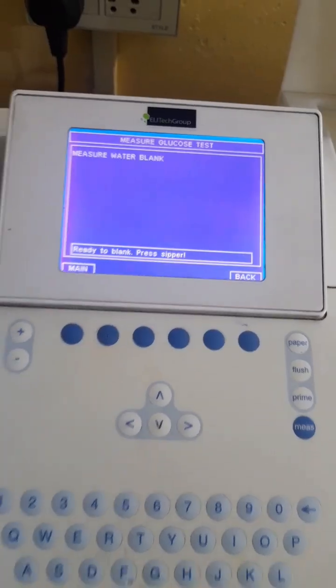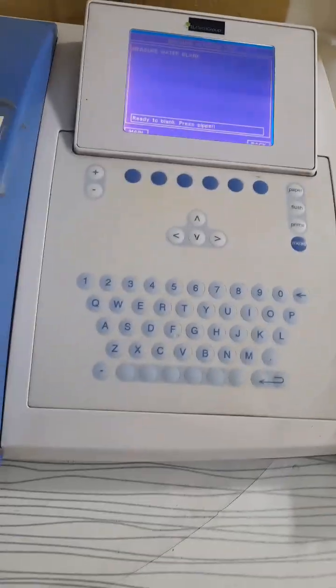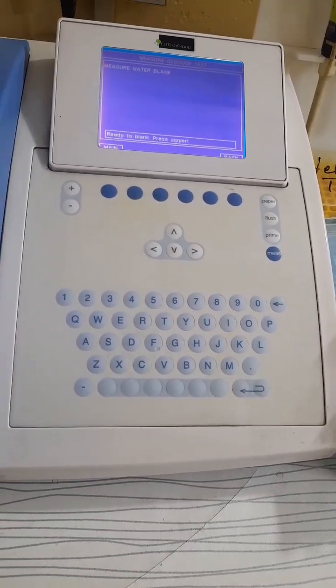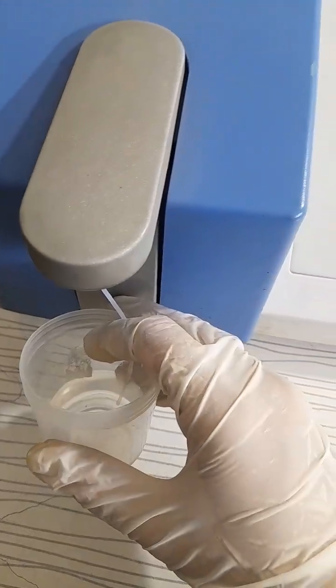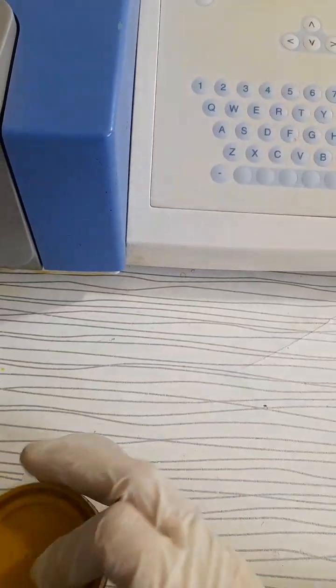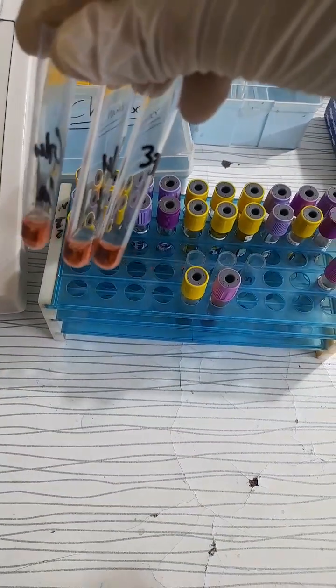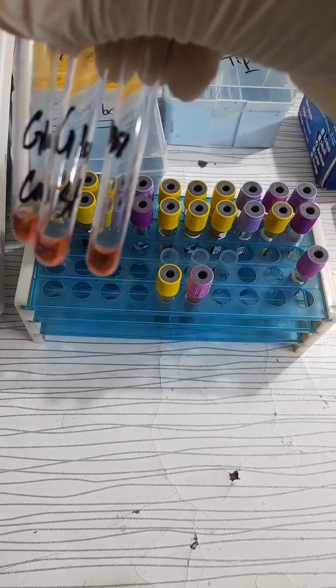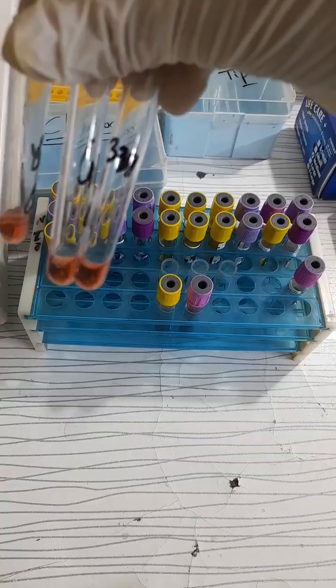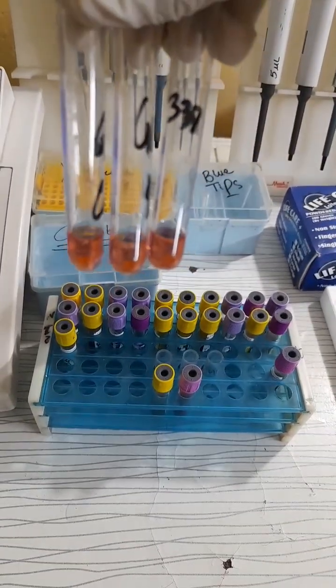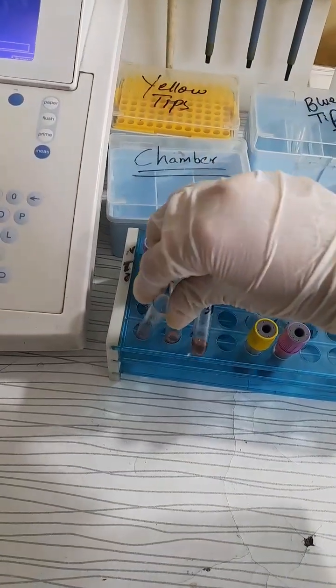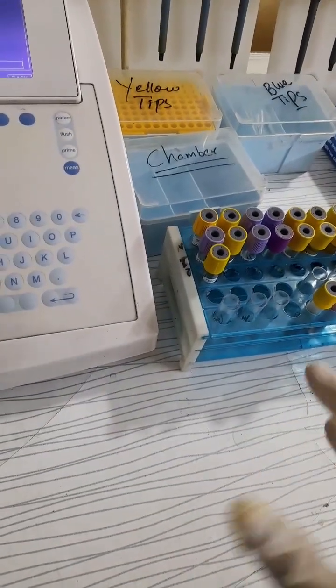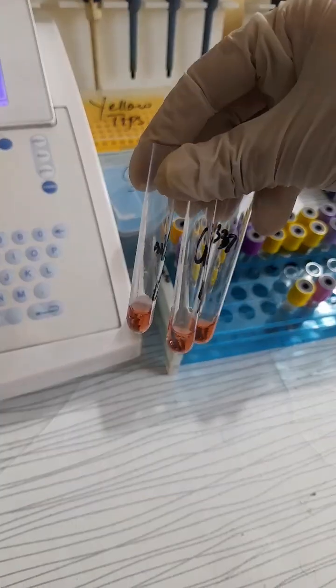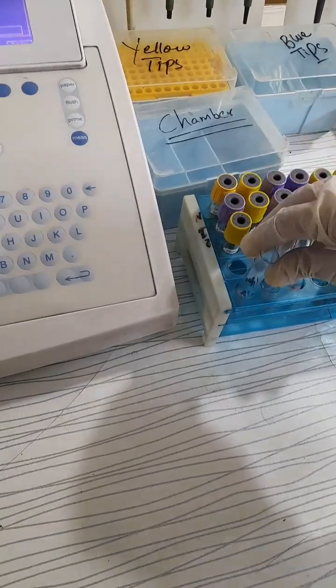Press enter. Ready for the blank. Press the sipper. As I already prepared the sample, the rest is for the incubation. Now let's see what's happening to the sample. The first one is my calibration, the second one is a standard, which is run as a sample, and number 3 is my sample. You can see there is a huge change in the color. This is because this is an endpoint method, and in the endpoint method the concentration of the color change is directly proportional to the concentration of the glucose present in the sample.